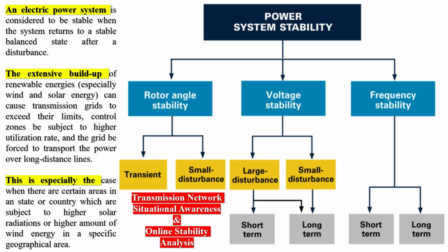At the same time, the rise of inverter-based renewable energies, which are replacing large power plants, leads to a reduction of the rotating mass instant reserve. This fundamentally changes the dynamic behavior of the power system. From a grid management point of view, changes underway in the generation mix have changed the dynamic behavior of the system, and the increasing volatility results in higher complexity and a variety of operational situations which have to be carefully observed and controlled in a predictive and proactive fashion.